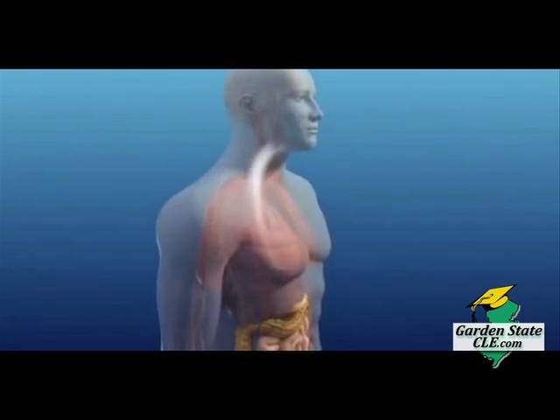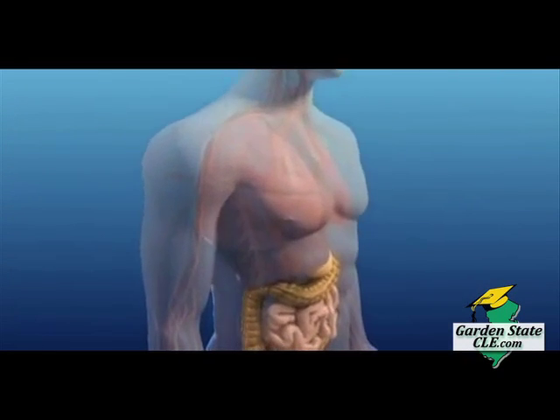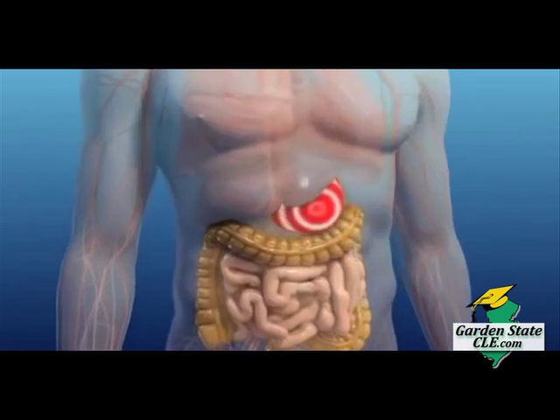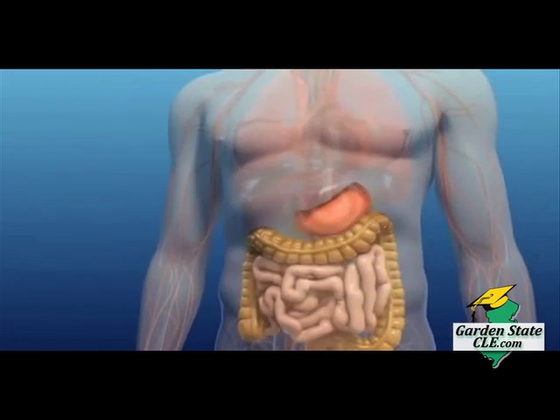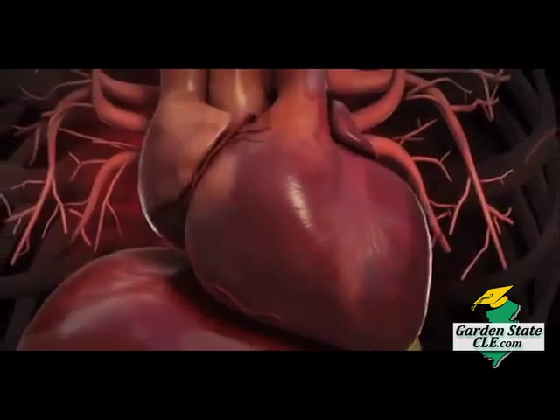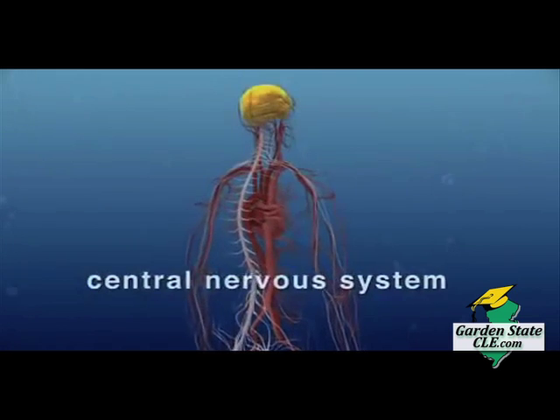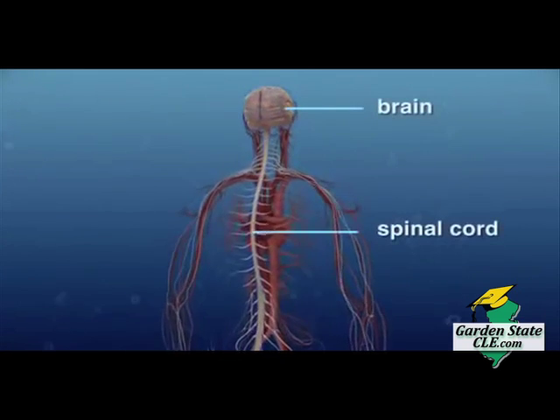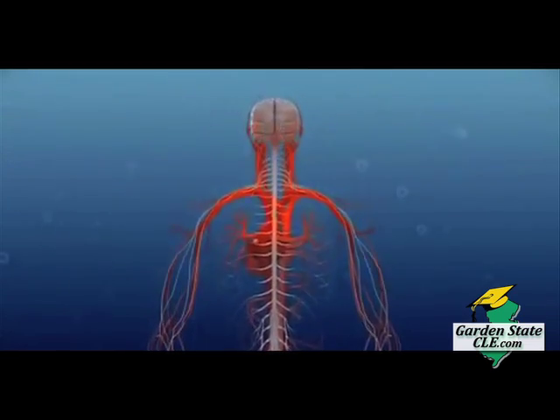What happens is the breath comes in and then exits out, and the molecules of alcohol - ethanol, hopefully, that's what 9.5 microns is specific for - absorb some of the signal. The difference between the signal coming in and the signal going out is how much alcohol went through the chamber. Now, there's a big difference between the Alcotest and the old breathalyzer.